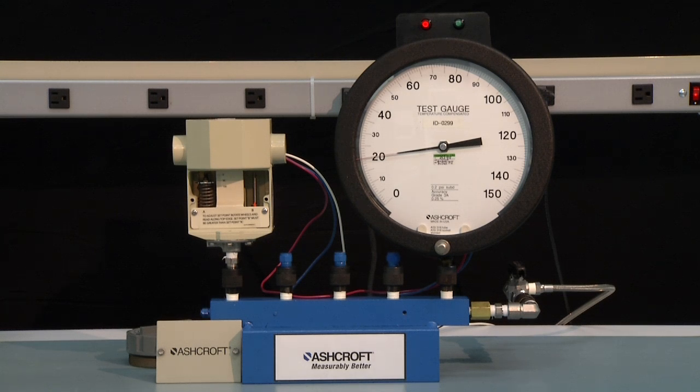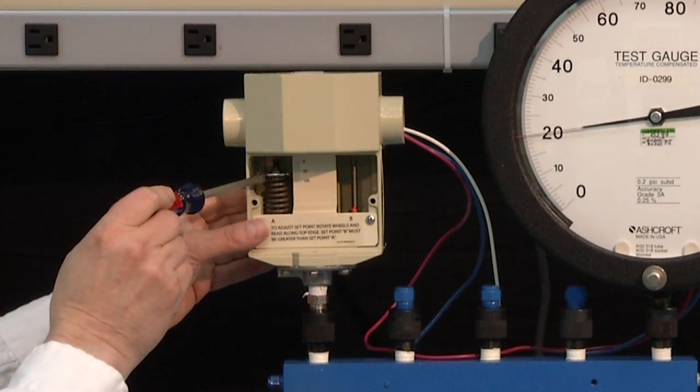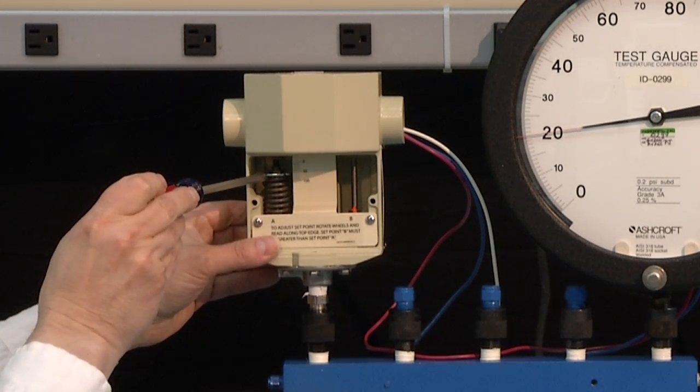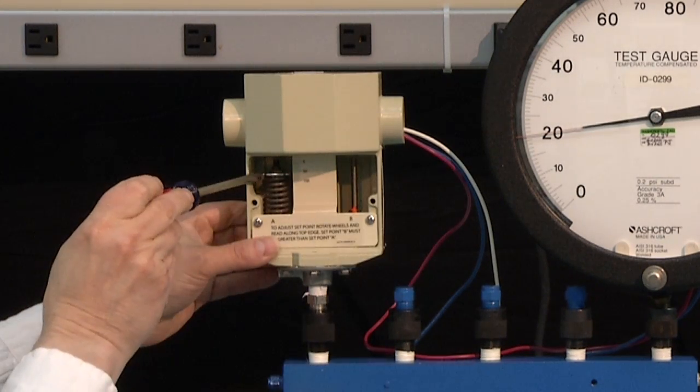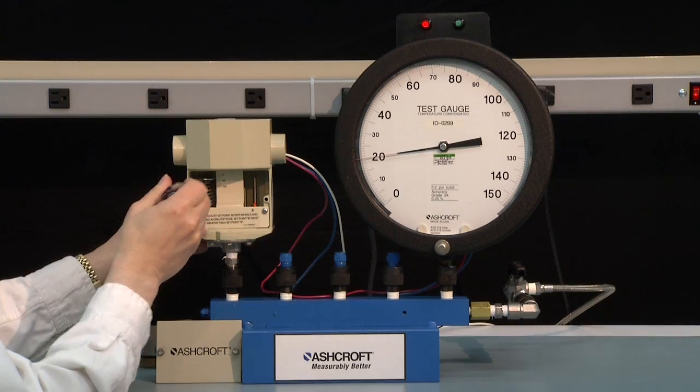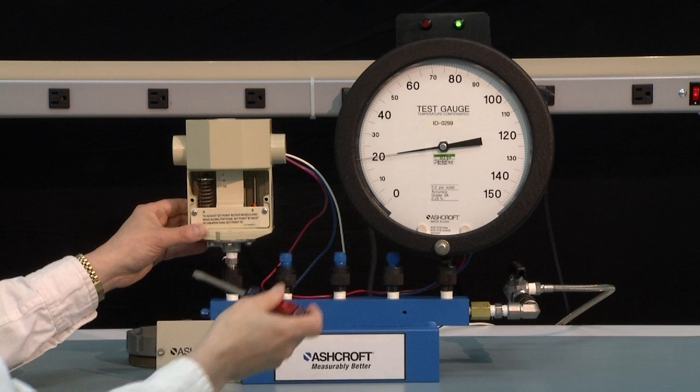With that, we are going to turn the adjustment wheel counterclockwise. That will lower the set point of the switch. We will turn it all the way down until the switch turns on at 20. So we are turning it counterclockwise to lower the set point. Now we just turned back on.